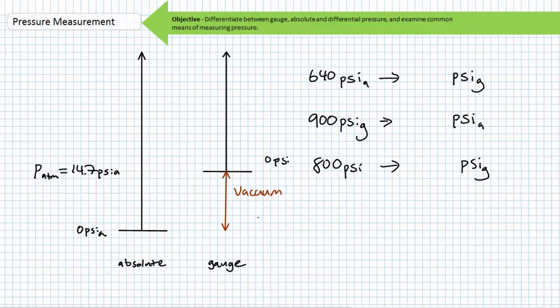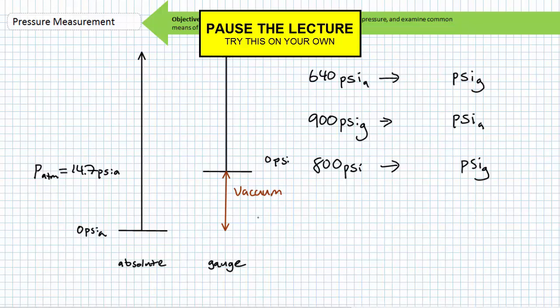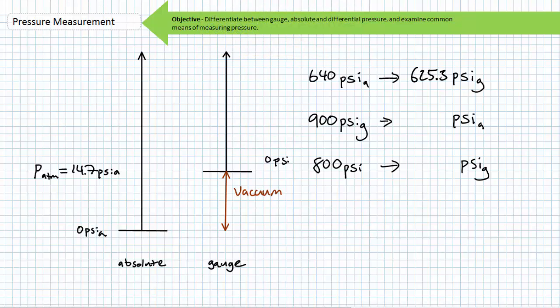Let's put your understanding of this simple concept to the test. Given the following pressure measurements, convert to the desired scale. Don't make this hard and don't dork this up. By all means, pause the lecture and take your best shot. A reading of 640 PSI absolute is equivalent to 625.3 PSI gauge. A reading of 900 PSI gauge is equivalent to 914.7 PSI absolute. Finally, 800 PSI gauge is equal to 800 PSI gauge. Again, units of PSI without a modifier is assumed to be gauge pressure. I must again emphasize that fluid power systems customarily use gauge pressure with common atmospheric conditions being the zero reference.